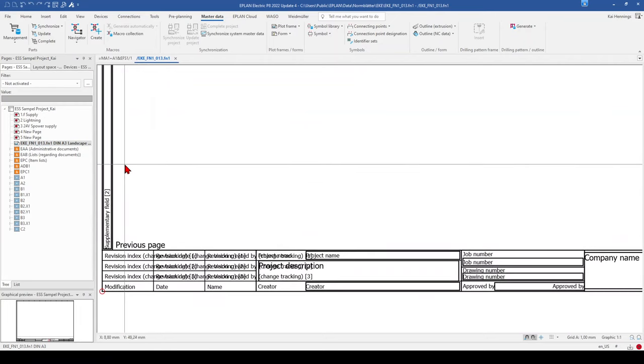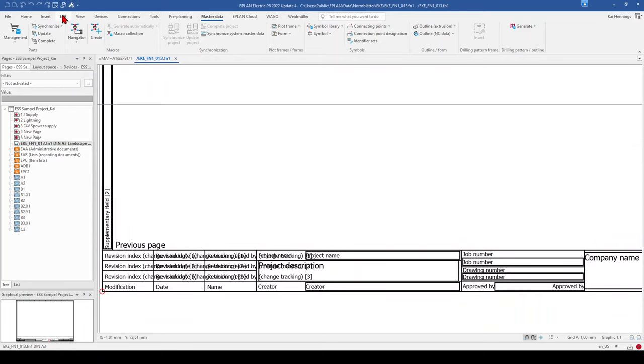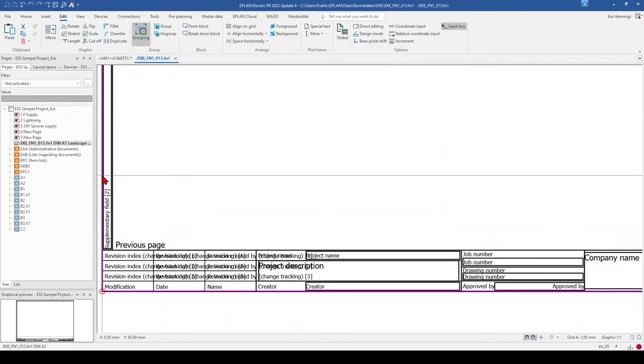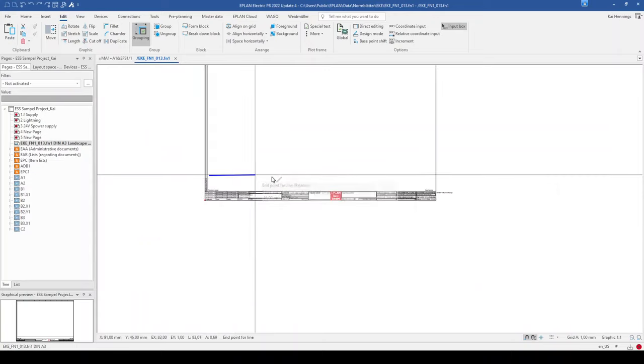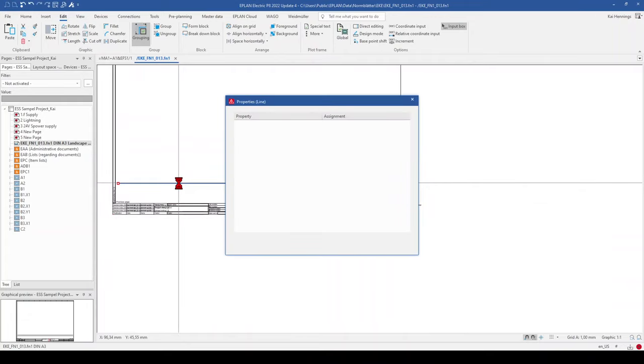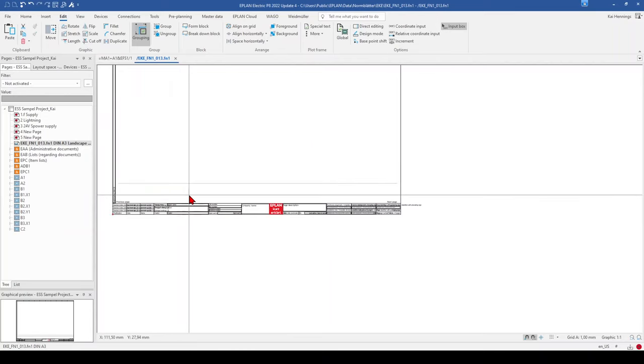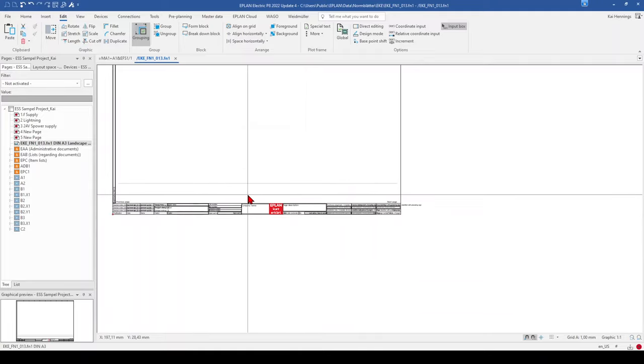We set this to 45 mm and move up a little bit. If it's difficult to get exactly Y=45 mm, you can go to Edit, Coordinate Input, and click on 45 mm — then it jumps automatically to 45 mm. When we press CTRL+F2, we insert a line. We then go to the properties of this line and make it invisible. Now we have an invisible line which will not be printed on your drawings, but in your circuit diagram you can see where the contact image is and avoid placing symbols above it.